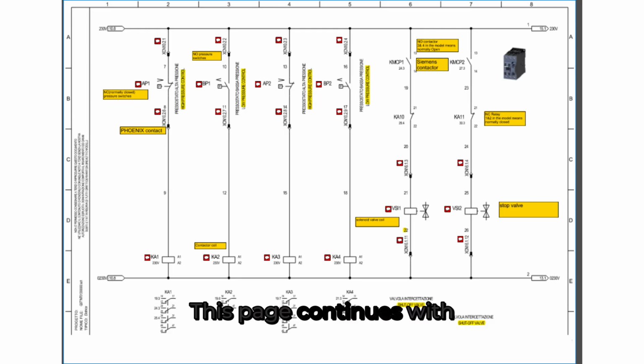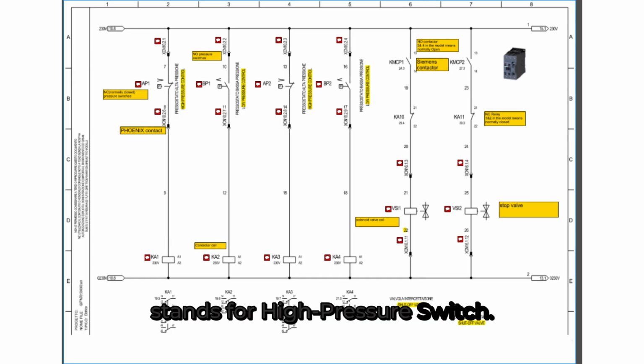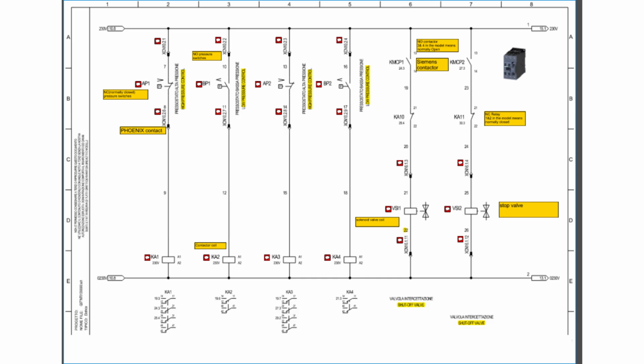This page continues with the 230 volt control power from the previous sheet. Starting from the left, you can see the Phoenix Contact terminal blocks, which serve as wiring junctions between field sensors and internal control components. The first safety devices in this circuit are the pressure switches, labeled AP1, BP1, AP2, and BP2. Each refrigerant circuit, Circuit 1 and Circuit 2, has two pressure switches. AP stands for high pressure switch. BP stands for low pressure switch.